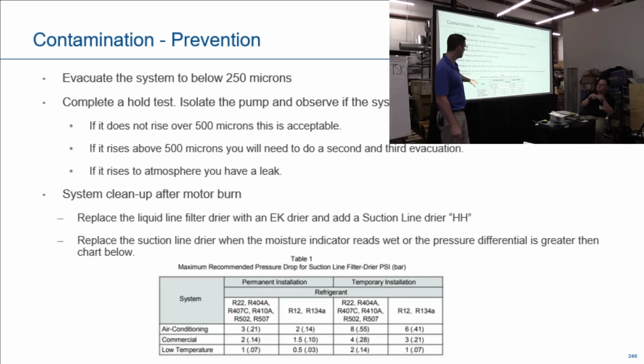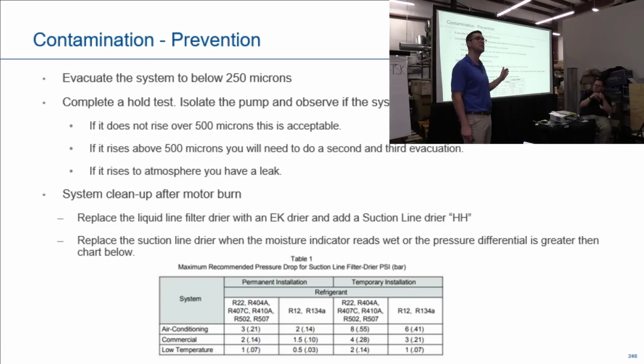This is for some old refrigerants, but permanent installations, you do not want the pressure. For example, for 404 here, for low temp application, you wouldn't want that filter to go over 1 psi or you'll have to cut it out. Most manufacturers that sell filter dryers for burnouts, they'll tell you after so many hours you should be pulling that out of the system. The reason that's so bad is because of the compression ratio, right? There you go, bang on.